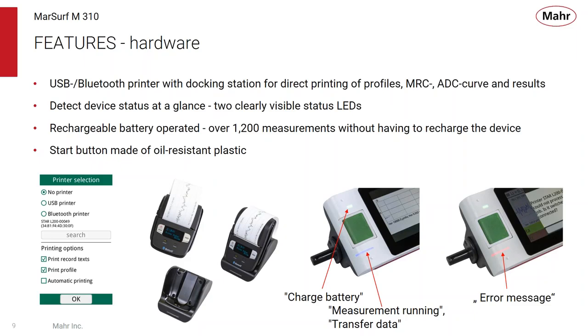On the bottom, you can see there are 2 LED displays for the user, one signifying that the battery is charging, the other signifying that the measurement is running or transferring data. That's a blue light. If that light turns red, that's an error message to the user, and you can find out what is going wrong with the system.